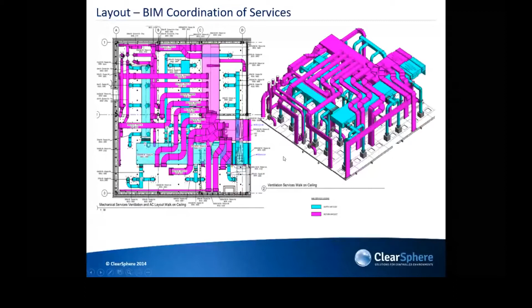Here's a photograph of what you're looking at above the ceiling, showing the amount of space available. Each leg supplied into a terminal housing, which contains the HEPA filters, had its own attenuator, meaning it was extremely quiet, giving a high quality finish for the people operating within the facility, since moving a lot of air will normally cause noise.